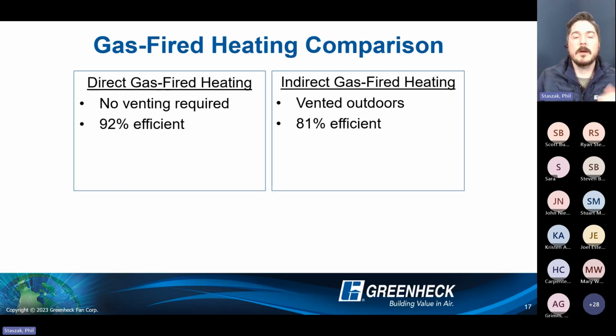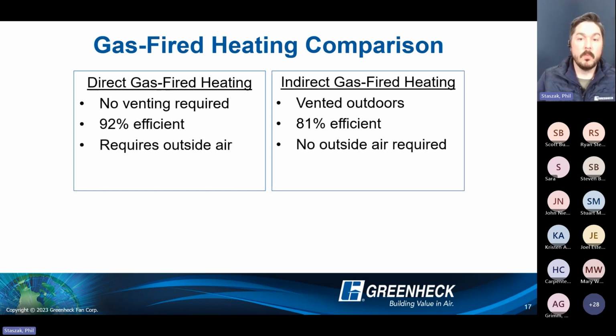If it's makeup air, you can typically get away with a direct gas fired application. We'll talk about why indirect is even in conversation. Direct gas requires outside air. The advantage with indirect is you can do a full recirculated option, standard on DOAS type applications, where you can do literally no outside air and just recirculate 100% of that air across the indirect gas fired heat exchanger. Direct gas fired does require that outside air for bringing those byproducts of combustion down.